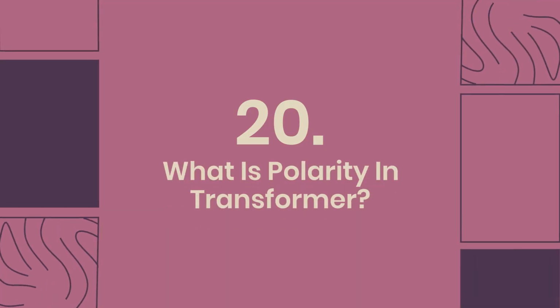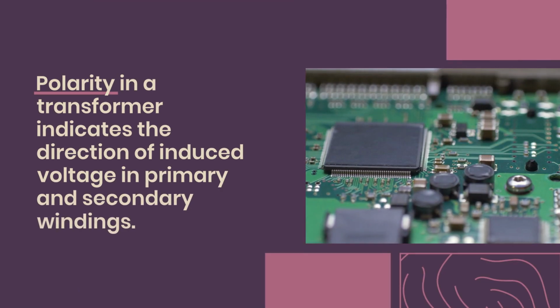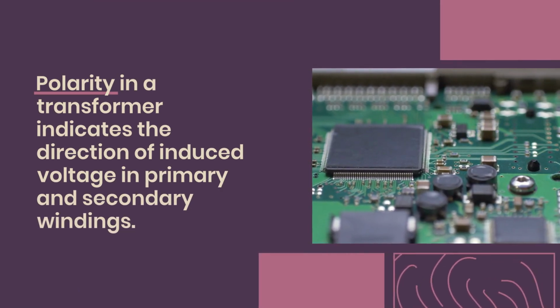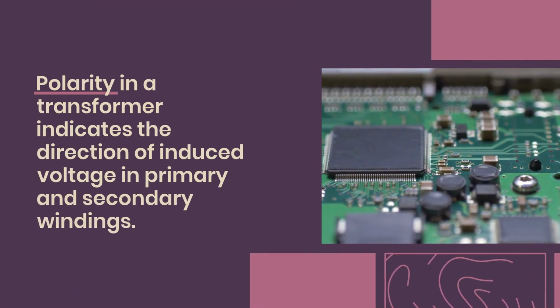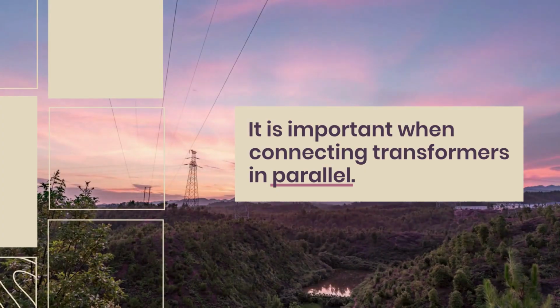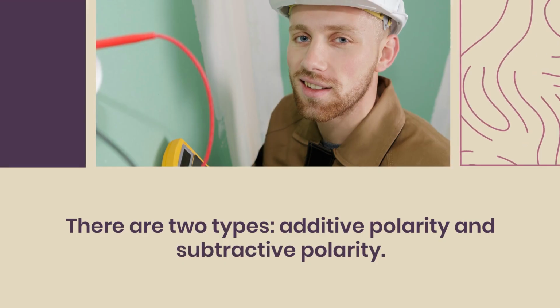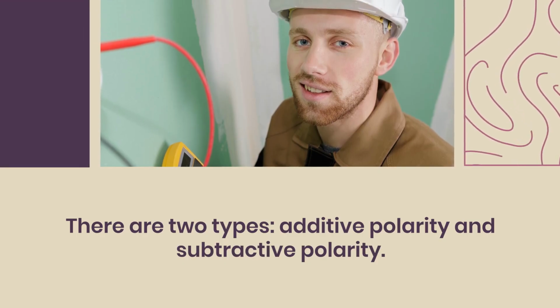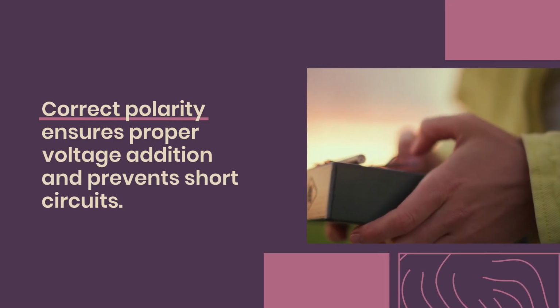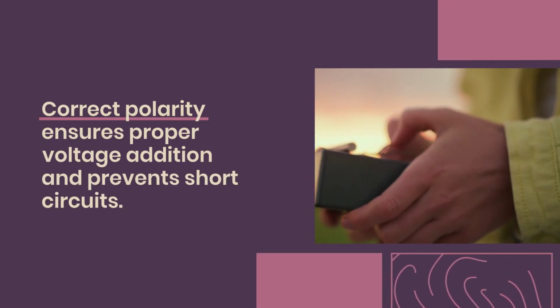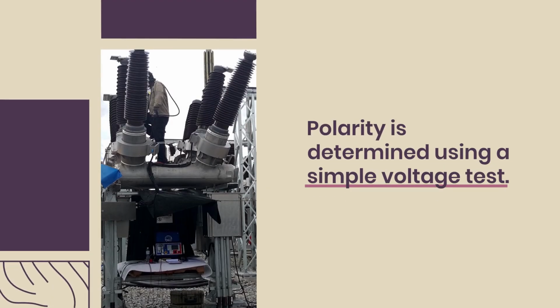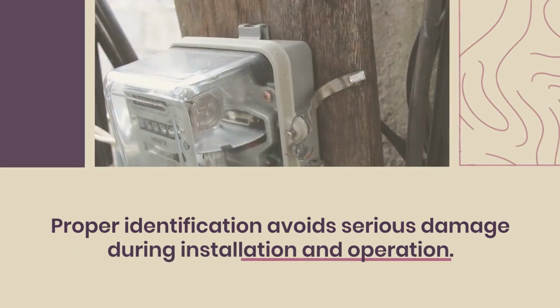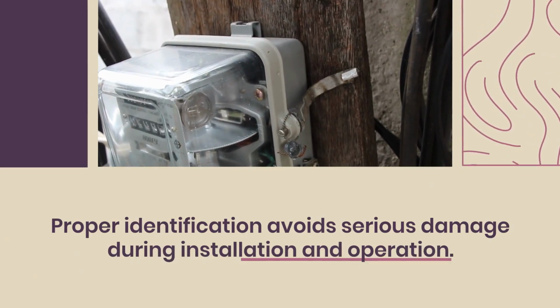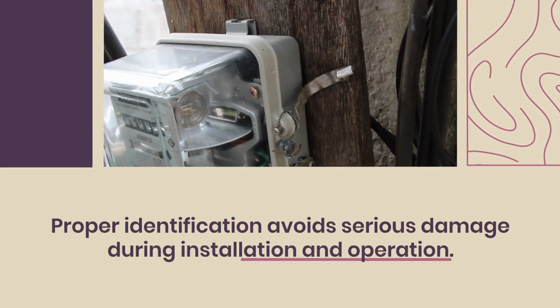20. What is polarity in transformer? Polarity in a transformer indicates the direction of induced voltage in primary and secondary windings. It is important when connecting transformers in parallel. There are two types: additive polarity and subtractive polarity. Correct polarity ensures proper voltage addition and prevents short circuits. Polarity is determined using a simple voltage test. Proper identification avoids serious damage during installation and operation.